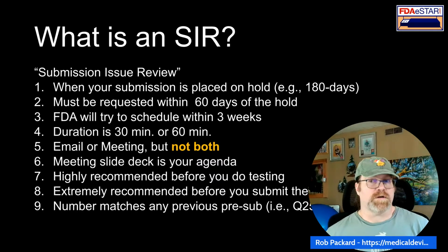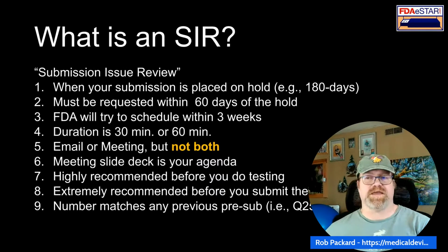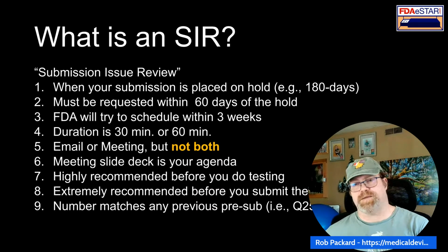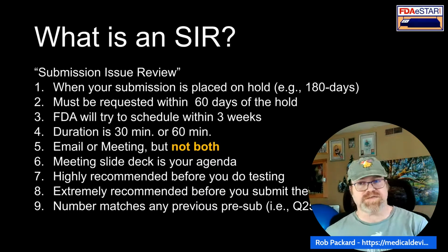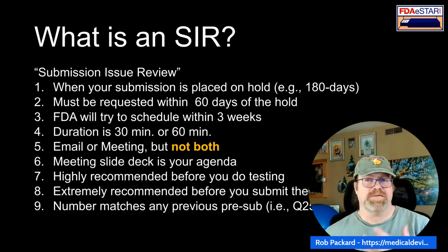And therefore, if you're going to submit a slide deck with an agenda for an SIR meeting, that is the entire thing. All your questions are there, your agenda's there, everything's in that slide deck. So for an SIR meeting request, that slide deck has basically everything the FDA needs to know in it if you did it well. If you don't have everything you need in there, not the agenda, not the attendees, not the timing, not the login information, there is a scenario in which every single one of those missing things is a problem. And that's why we have a template that we use for our SIR meetings to make sure we don't forget something.